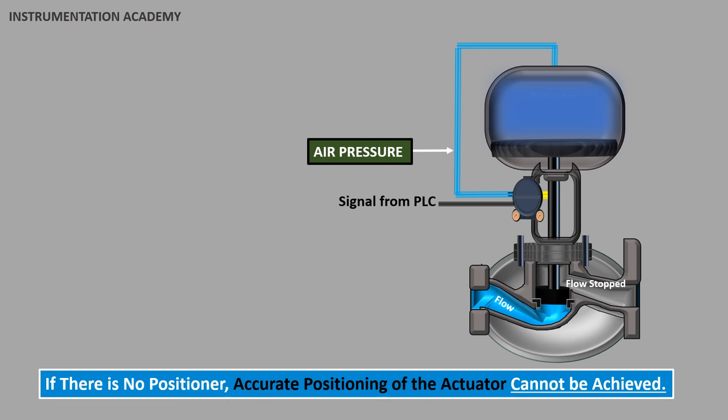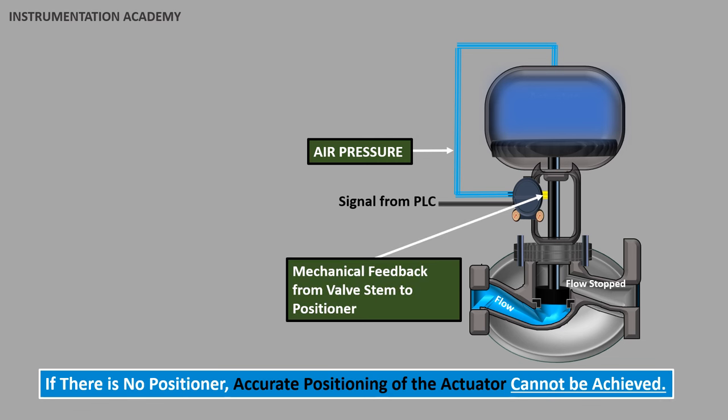So when accurate and faster control is required, a valve positioner is used. A valve positioner will have a mechanical feedback from the valve stem which will inform the valve positioner about the exact position of the valve stem.